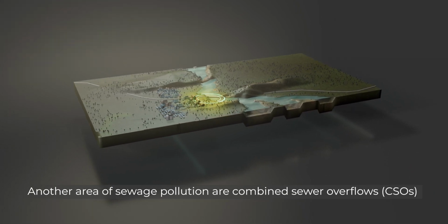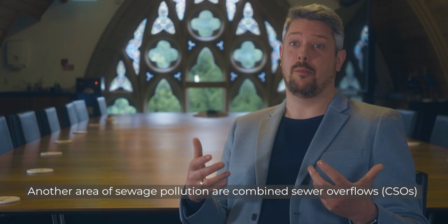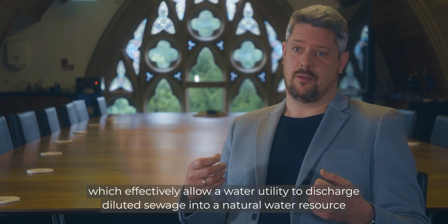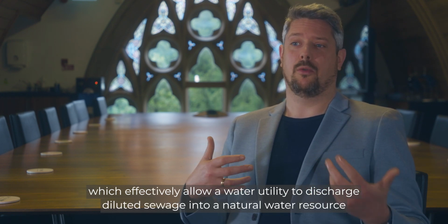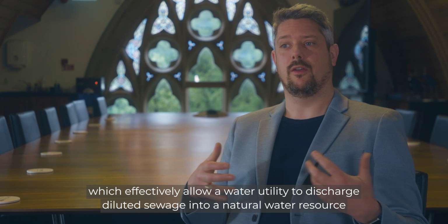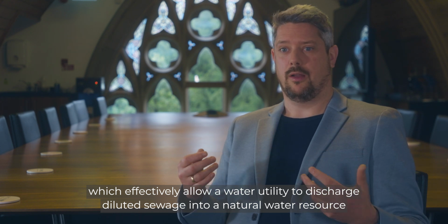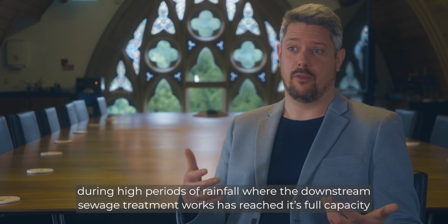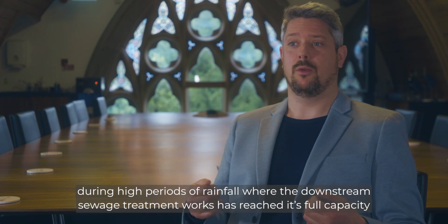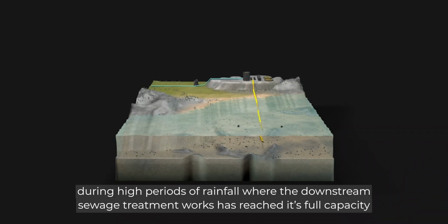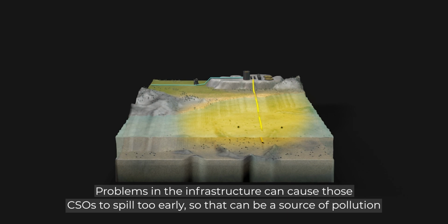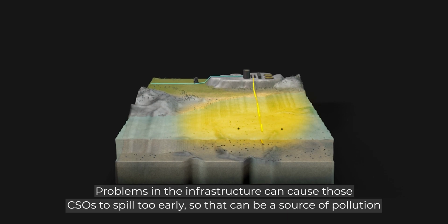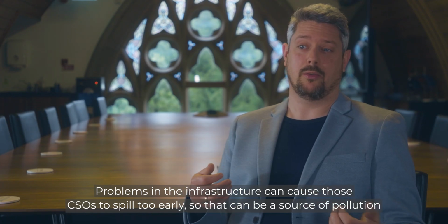Another area of sewage pollution are combined sewer overflows, which effectively allow a water utility to discharge diluted sewage into a natural water resource during high periods of rainfall, where the downstream sewage treatment works has reached its full capacity. Problems in the infrastructure can cause those CSOs to spill too early, so that can be a source of pollution.